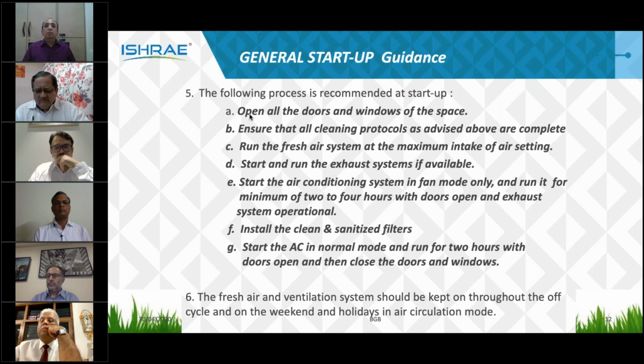Start the air conditioning system in fan only mode. Run it for a minimum of 2 to 4 hours with doors open. with exhaust system operational, and then install clean and sanitized filters. Start the AC in normal mode and run for 2 hours with doors open, and so on. The fresh air and ventilation should be kept on throughout the off cycle as well as on weekends and holidays in air circulation mode. Next slide.